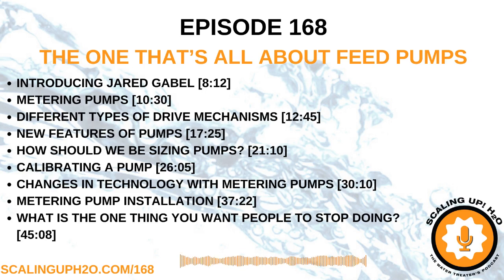And one of the other things is, how do you want to control the pump? Are you going to be setting it and forgetting it because it's just rocking in at a constant feed rate and you've got it dialed in with your process, the water quality never changes? Or could it be that there is a need to adjust based on flow? So most of the time I'm seeing installations and applications where the dosing pump is actually flow paced off of a main process flow. And so then you have a flow meter that can send a signal either directly to the pump or through some kind of a PLC to change that signal and then send an analog signal or pulse signal onto the pump. So those are three of the main things that will get me to basically the ballpark of what pump needs to be used for that application.